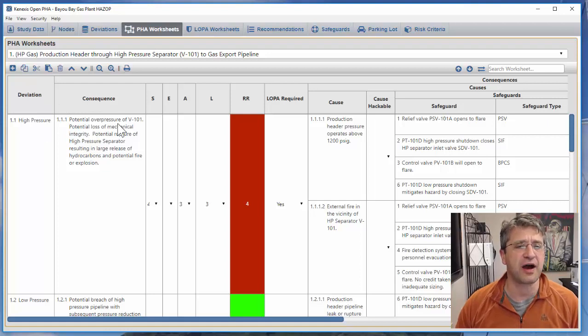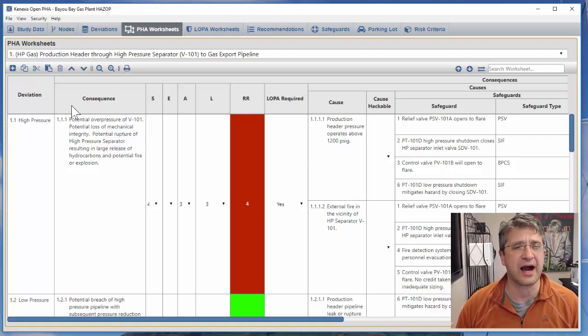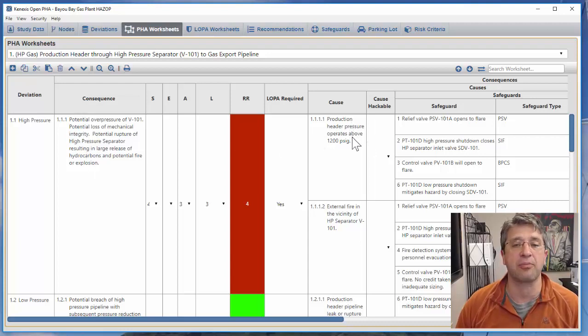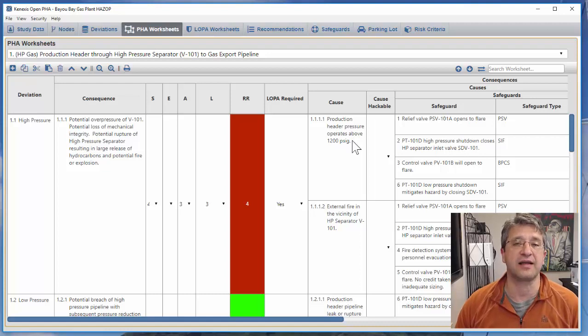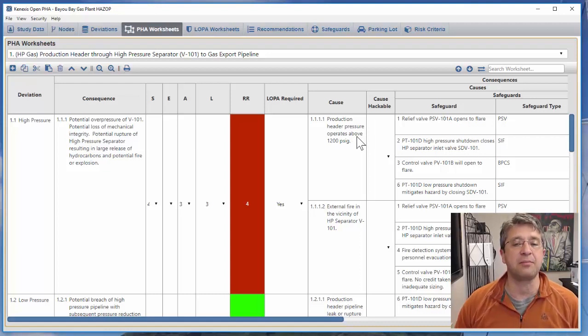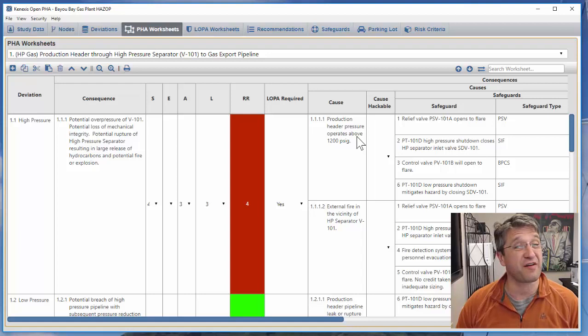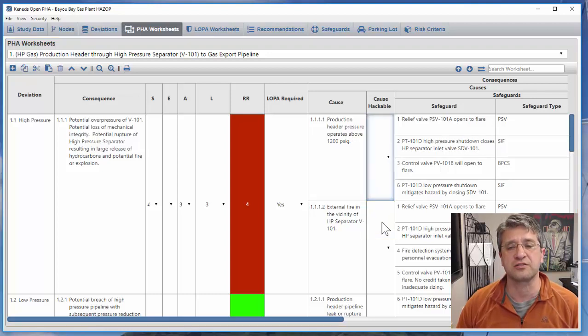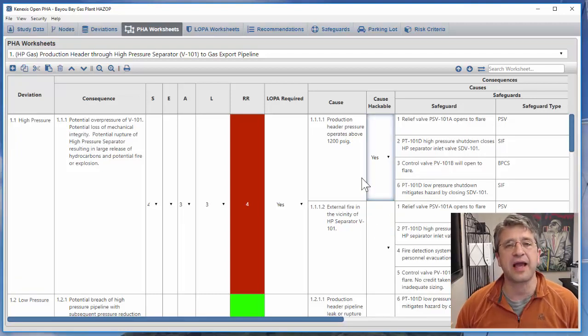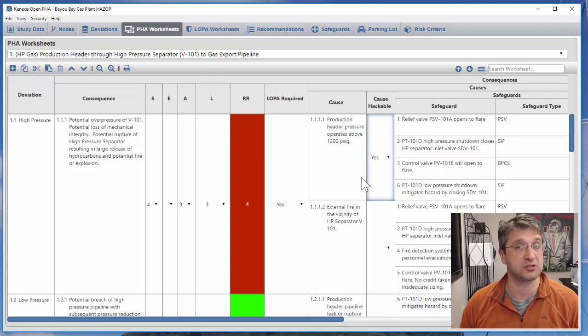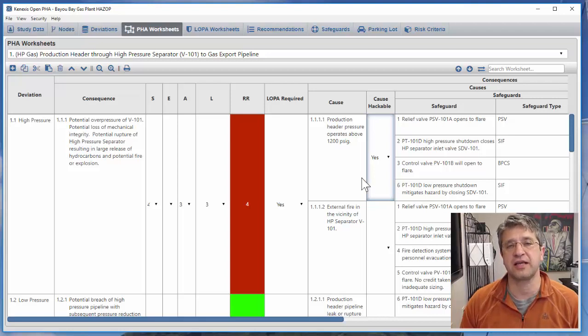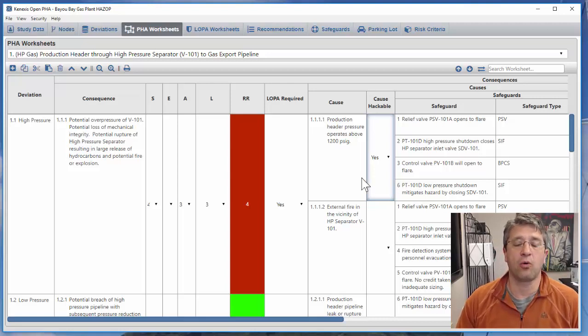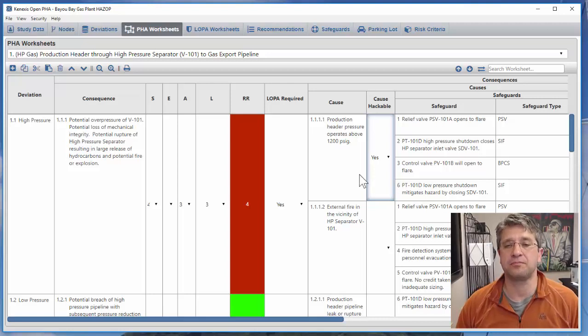The first deviation of high pressure was determined to be generated by the production header operating over its design limits. The design pressure in that production header is set by the basic process control system of another facility. Because it's the basic process control system we're going to say yes it's hackable. What makes something hackable? If it's in a device that contains a microchip, some sort of computer processor, and that computer processor is able to speak on a network with a routable protocol like IP or Modbus, then the device is hackable.